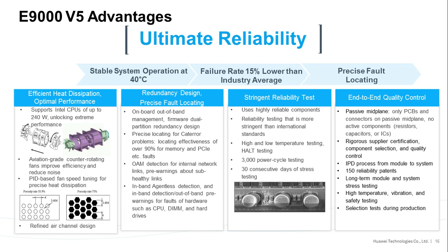What fault locating and reliability design measures have been taken to lower the fault rate and improve reliability? Measures include efficient heat dissipation, redundant design, stringent reliability tests, and end-to-end quality control. Another point I'd like to emphasize here is the passive backplane, which greatly reduces backplane failure rates. Failure of the backplane is generally high if it is configured with resistors, capacitors, or ICs.